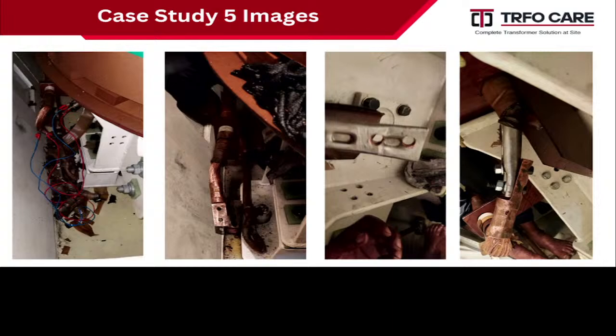See, the finding was Y-phase neutral end found open, Y-phase LV to neutral connection found open. The crimping ferrule, the lead of the bottom LV winding, was removed from the crimping. So the same fault was attended at site by additionally putting one ferrule and crimping the joints. And after heating and vacuum process, we started the transformer. This transformer is running for last 2 years.